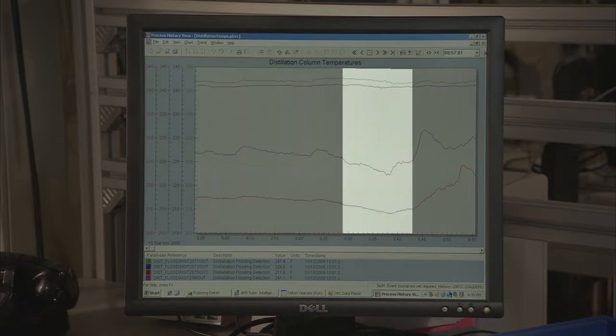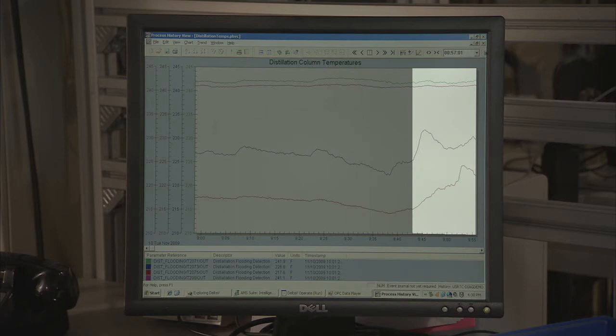Now, under flooding conditions, the packing bed temperatures will start to converge. However, this temperature convergence usually occurs well after flooding has taken place and does not provide an opportunity to take any preventative action.